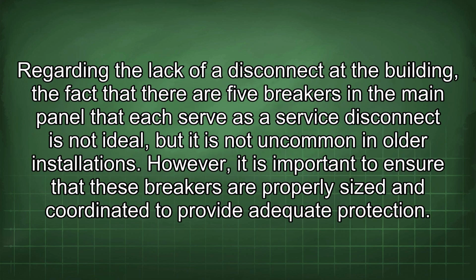Regarding the lack of a disconnect at the building, the fact that there are 5 breakers in the main panel that each serve as a service disconnect is not ideal, but it is not uncommon in older installations. However, it is important to ensure that these breakers are properly sized and coordinated to provide adequate protection.